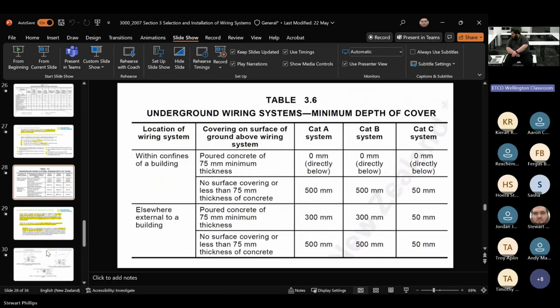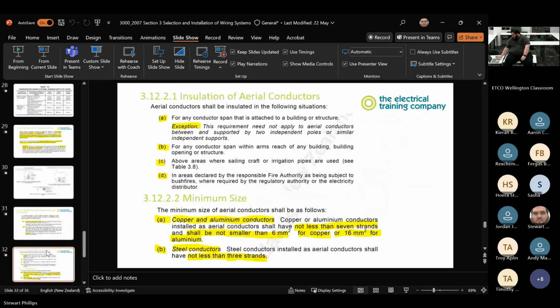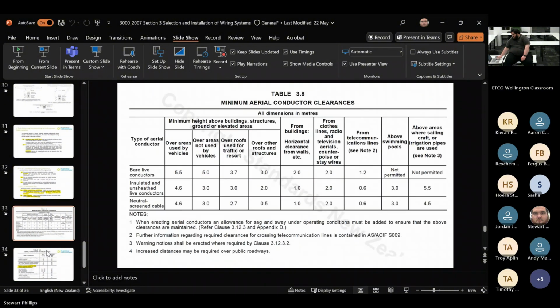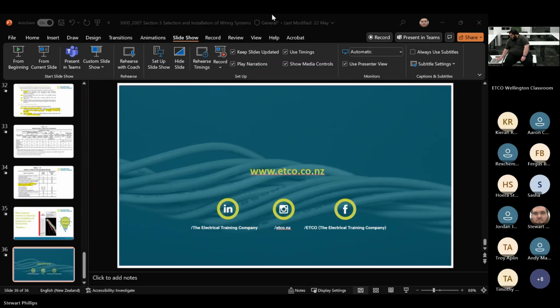This is where it talks about minimum depth of cover. So 500 for Cat A and B, where there's no surface covering, or less than 75 mil thickness of concrete. Within confines of a building. And elsewhere, it's pretty much the same. The only time it changes is when we're talking about concrete with a 75 mil minimum thickness. That's just more about the size. So insulated aerial conductors, it's a good read. Stop there. For that section, cool.